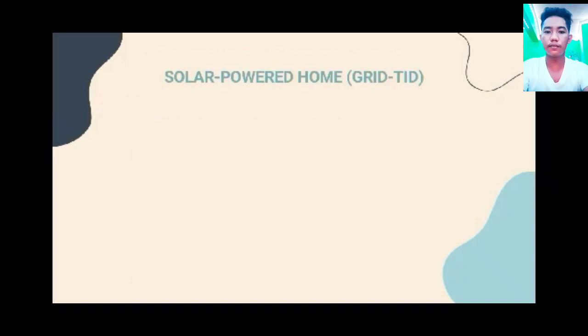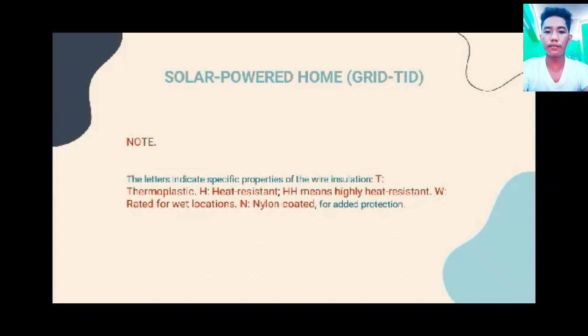So next, the letters indicate specific properties of the wire insulation. T stands for thermoplastic, H stands for heat resistance, HH means highly heat resistance, W rated for wet location, and N for nylon coated for added protection. Next. So this is the AWG cross-sectional area in centimeter. So meron po dito yung size, cross-sectional area, weight, overall diameter. So dito po yung mga sukat ng mga wire.